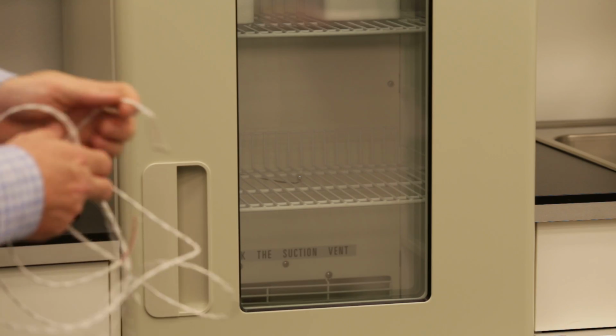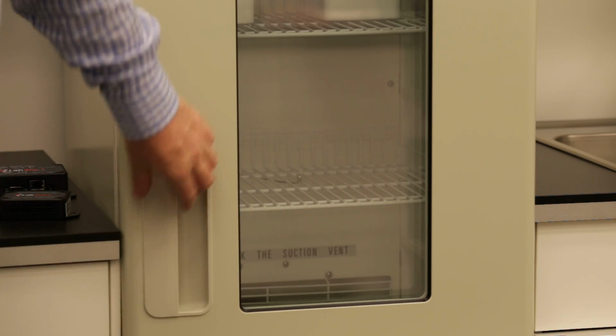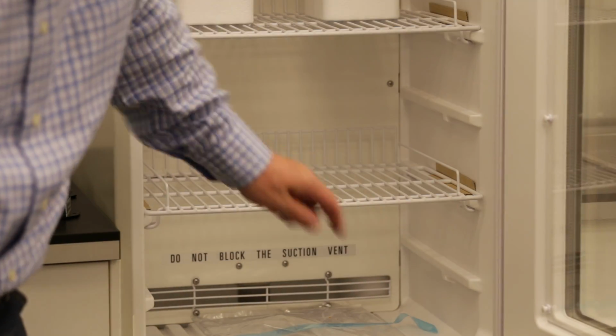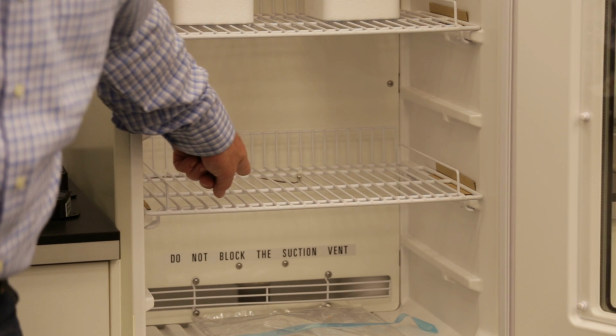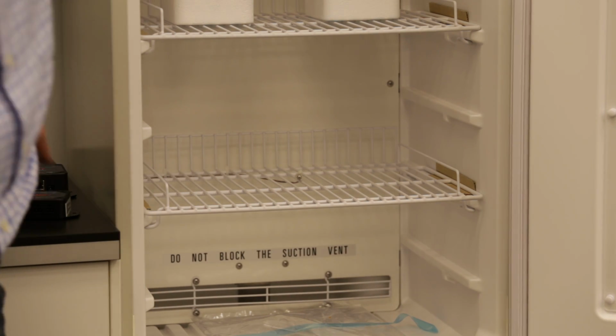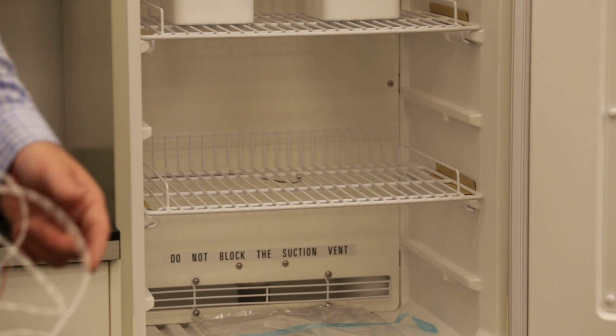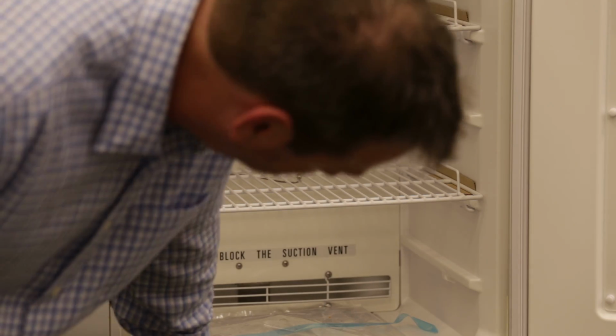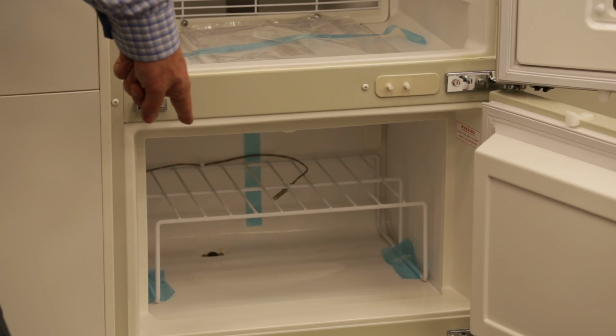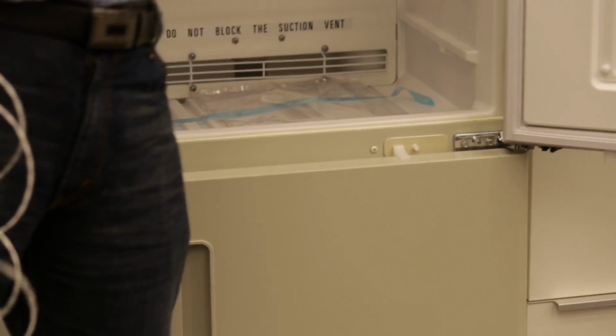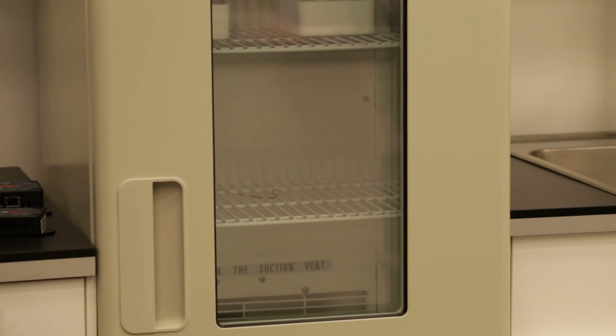You have to consider where it's being installed in the equipment. In this case, we want to monitor the air temperature in the center of the unit. So we're using a couple of feet of the probe to be able to go through the access port. Same thing for the freezer section. We're going through the access port and we're using a couple of feet for the probe. So that leaves us roughly 8 feet left to run to the transmitter.